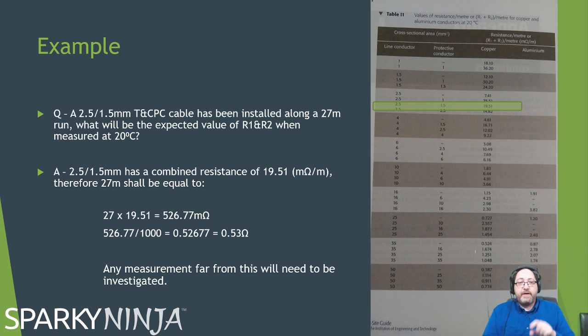It doesn't take an idiot to press a button and for a number to appear. The genius is being able to go, that number's no good, that number's not right, and then working with that. So let's say we've installed a 2.5 mil and 1.5 mil twin and earth, 27 meters in length for a radial circuit, and we're going to test at 20 degrees, so it's a de-energized circuit.